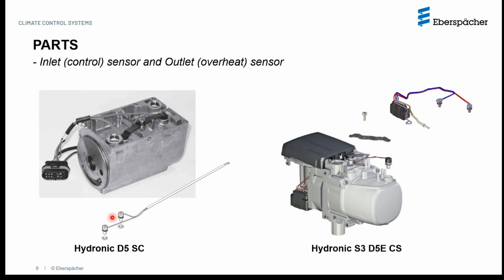That means if either one of these sensors goes bad, you have to replace this entire assembly. You can also see that these sensors have O-rings around them, and these O-rings are supposed to be replaced each time you tear apart a heater and rebuild it. These O-rings are available as spare parts on their own. You can see how the sensors are seated: the control sensor right there, and on the opposite side the overheat sensor, and this spring clamp firmly holds the two sensors in place.